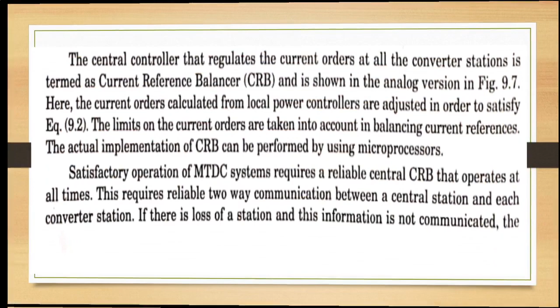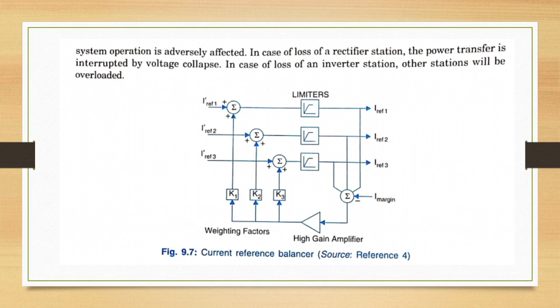Satisfactory operation of MTDC systems requires a reliable central CRB that operates at all times. This requires reliable two-way communication between a central station and each converter station. If there is loss of a station and this information is not communicated, the system operation is adversely affected. In case of loss of a rectifier station, power transfer is interrupted by voltage collapse. In case of loss of an inverter station, other station will be overloaded.